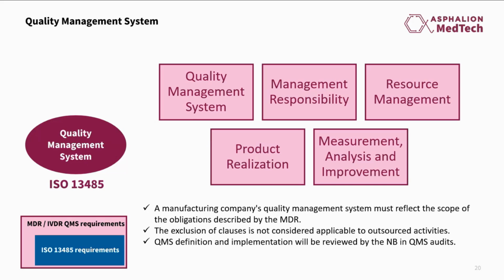For this, in Europe, we typically rely on compliance with a standard that, at the end of the day, represents the regulatory state of the art. So for the purposes of the quality management system, we have ISO 13485. By complying with this standard, you also have presumption of conformity with the medical device regulation requirements for the quality management system.